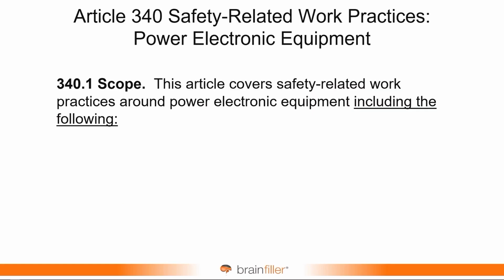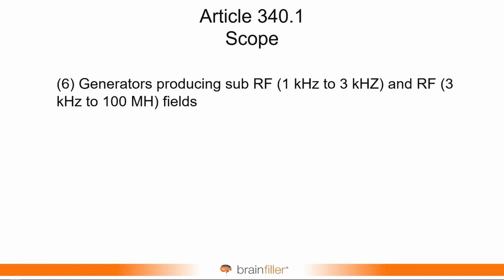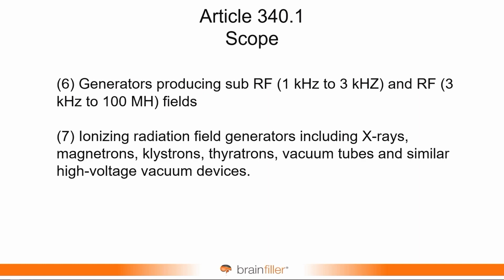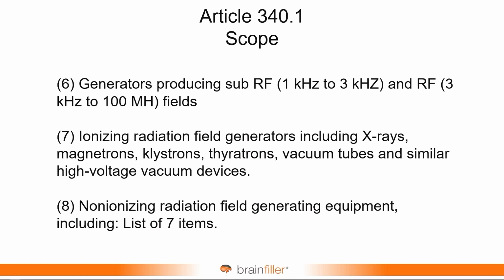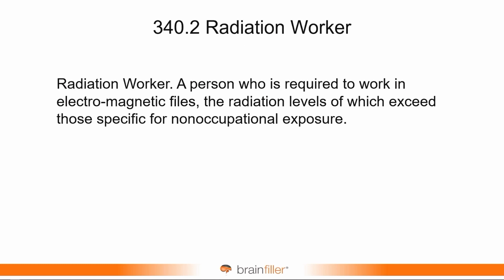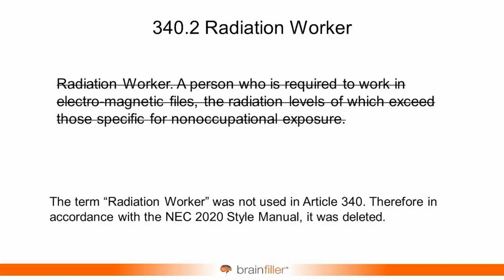Article 340, the scope was modified. The scope refers to power electronic equipment, including the following. And it was a pretty good list that's been expanded. We now have generators producing sub-RF and RF fields, ionizing radiation field generators, non-ionizing radiation field generating equipment. And then there's some items underneath number 8. So the scope was expanded. 340.2, the definition of a radiation worker, well, that was deleted because the style manual states that if you have definitions, but they're not used anywhere, then they don't belong in the standard. And if it did remain, which it didn't, it would have moved to Article 100 anyway.